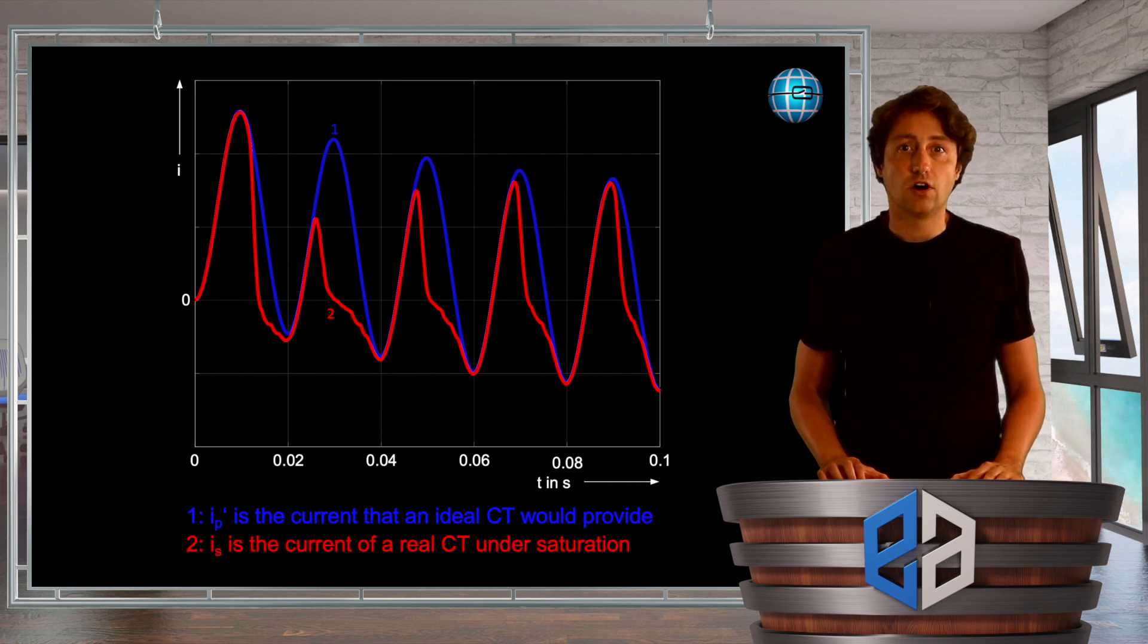Usually during normal operation this is not recognizable or predictable, but when the next fault occurs there may be an over or under functioning of the protection system due to the secondary current not being transmitted correctly by the saturated core of the current transformer.